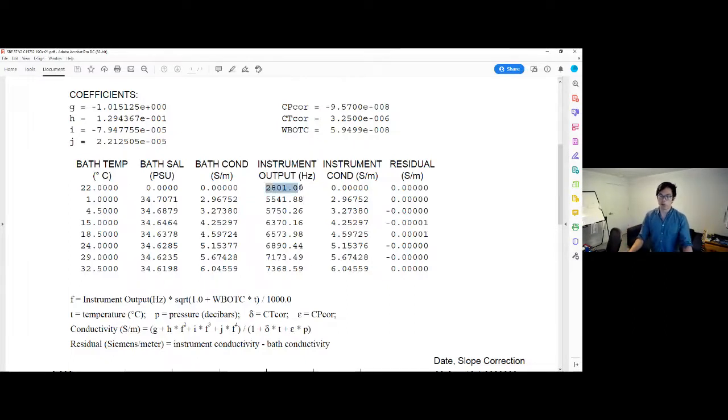What you can also do with the 0 conductivity frequency is just give yourself a quick sanity check on whether or not you need to clean your instrument. If your 37 is dirty, or I guess if the conductivity cell in your 37 is dirty, you can log some data in air and configure your 37 to output this raw conductivity value. I believe that's output format 1, maybe. Kim, maybe you could verify that for me.